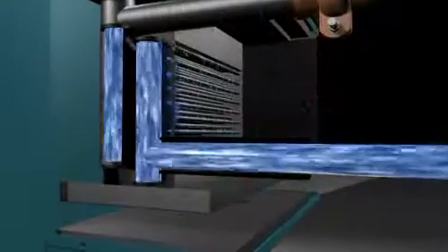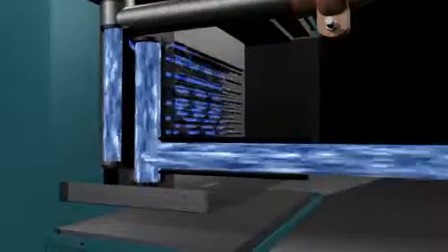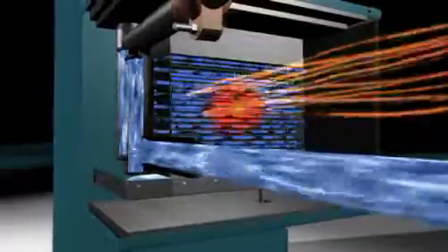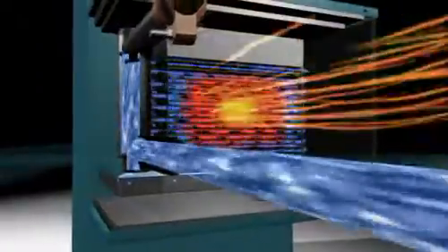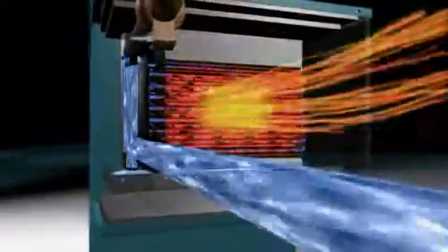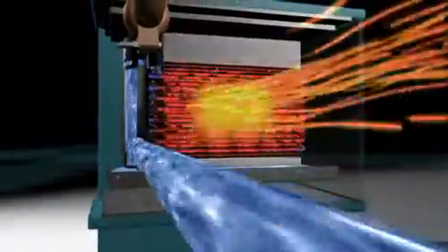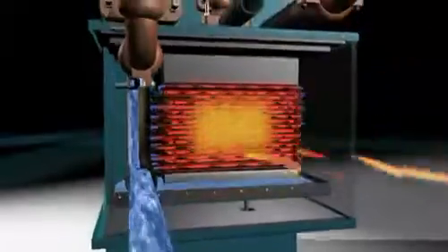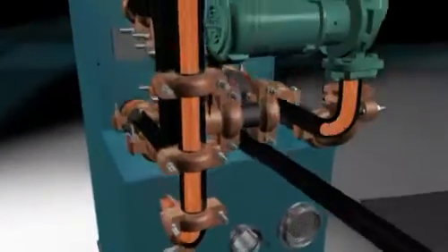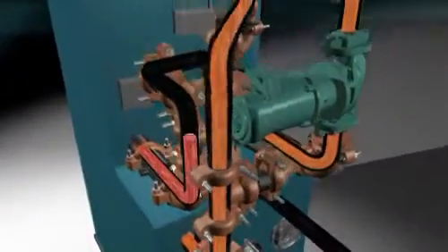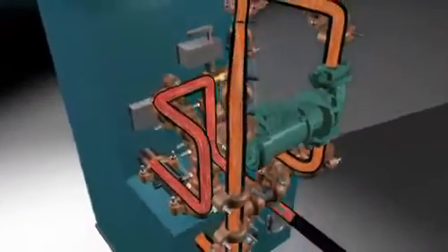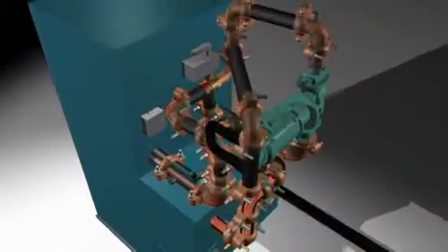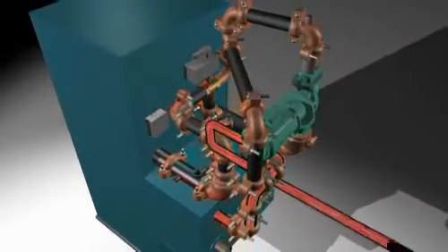Thermal Solutions uses hot flue gas, the discharged byproducts of gas combustion, to pass through the fins and heat water flowing in the tubes. This preheated water then enters the mixing loop where it is blended into the primary heat exchanger for more heat, or supplied to the system to satisfy heating demand.